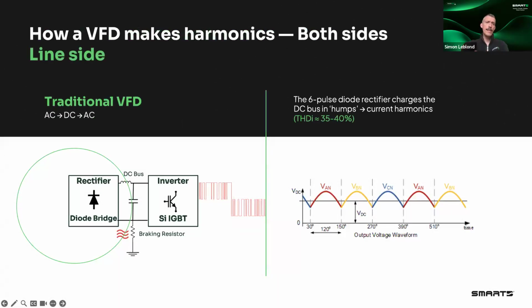data center? And so if we look into that architecture, on the line side, what is actually causing harmonics is the rectifier, a 6 pulse diode bridge, which charges the DC bus by drawing current in pulses from the grid. And you can see it on the right side of your screen. You've got these little humps, about 6 per cycle, and between those humps there's no current draw. So you're really having a pulsing current, and if you decompose that, you're getting integer multiples of the 60 hertz fundamental. In this case, the fifth, the seventh, the 11th, the 13th, and so on. And those harmonics are then flowing back towards the utility.